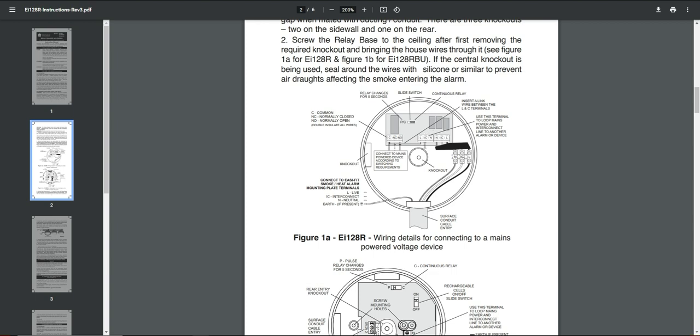You can connect your incoming cables, so you're gonna have live, neutral, and interlink. That interlink basically sends the signal to all other alarms in case of alarm. So you can take off one alarm, put that plate, connect, and then you can feed the alarm over that plate so you won't be able to see it. And then you have a relay output, output with common, normally closed, and normally open.